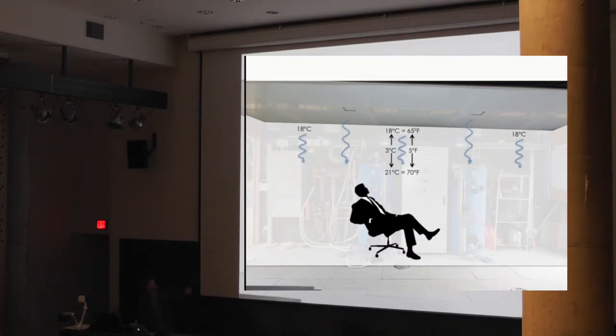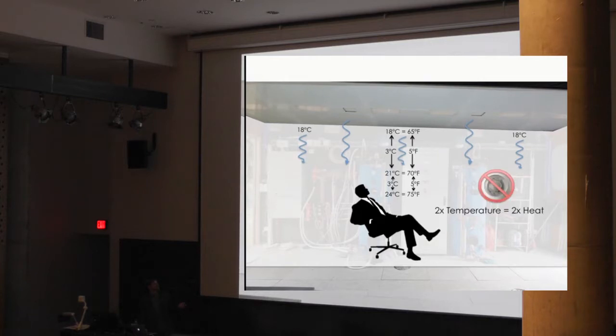But now imagine the physics of this system when the air temperature rises. What happened to the temperature difference from 18 to the room air? This was normal operation with a 3-degree temperature difference. Now I've increased the air temperature by 3 degrees, so it's essentially double the temperature difference. And what does temperature difference drive? Heat transfer. So the physics alone, by having a panel temperature close to the room air, means when the air temperature increases, 2 times the temperature difference equals 2 times the heat transfer.